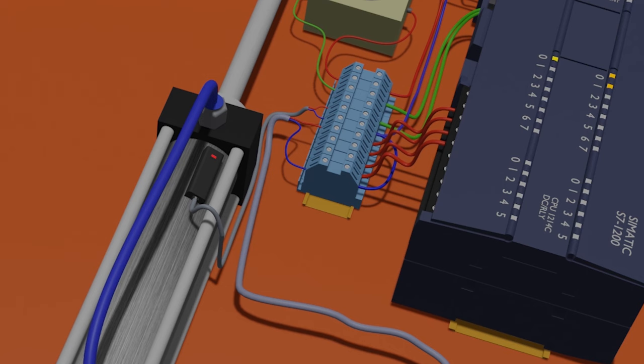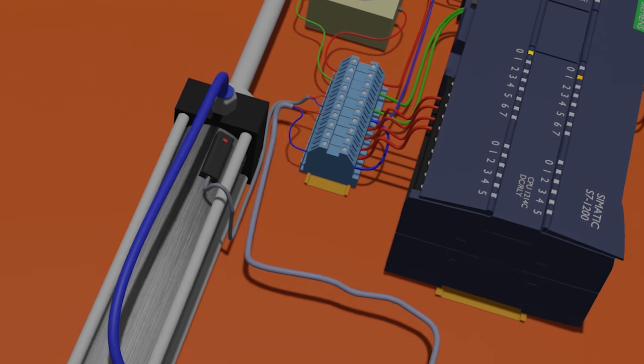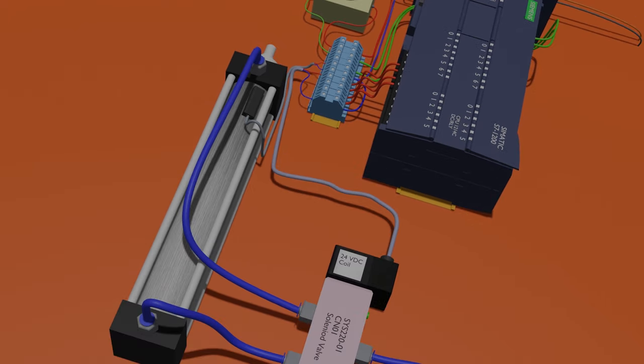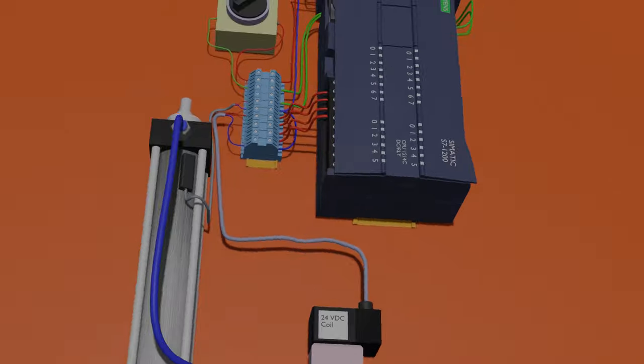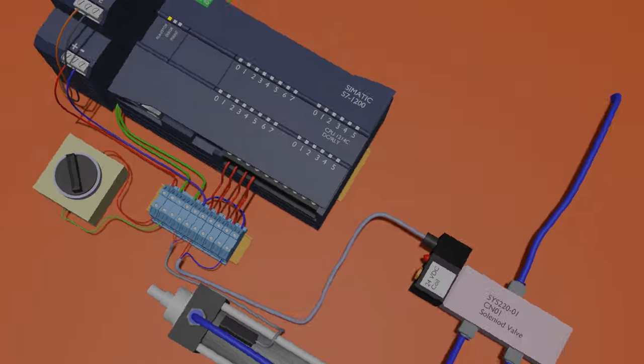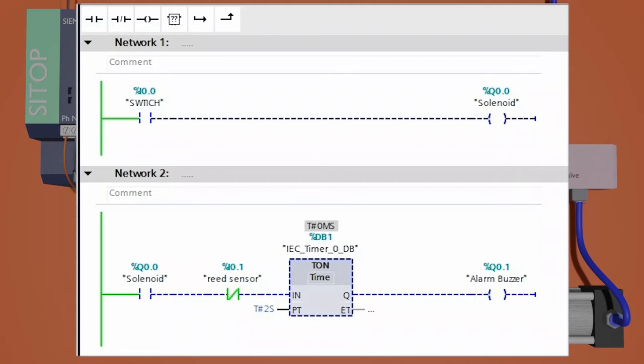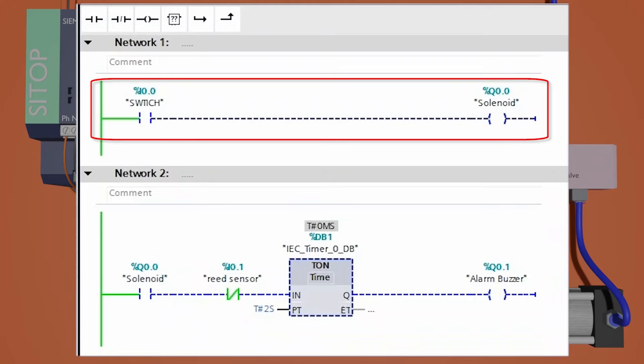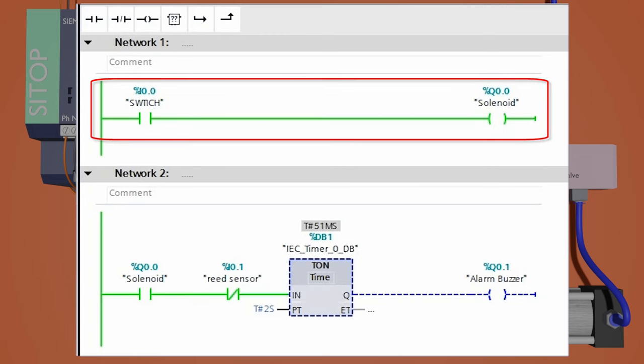Now go to the programming software and do some programming to make this work. In network one, we will take a normally open contact of the switch I0.0 and connect an output coil Q0.0 with it. So whenever the switch is activated, this normally open contact gets closed and it will activate the pneumatic solenoid connected at Q0.0 PLC output.